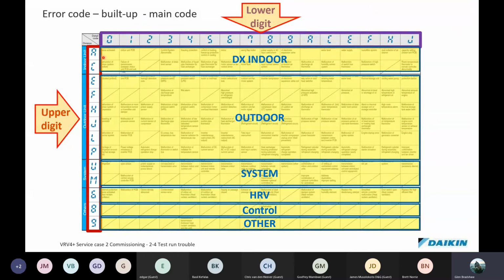The one thing that Daikin's been pretty solid with over the years, I've been with the product as an engineer and as a Daikin employee now for more than 30 years, 9 years with Daikin, and I can tell you now that the fault codes have been pretty constant. Any code starting with A or C will designate an indoor fault. Okay, and then they range through from 0 through to 9, and then with A, C, E, F, H, and J. So anytime you get an error code that starts with an A or a C, you need to be heading towards the indoor unit in order to fault find.